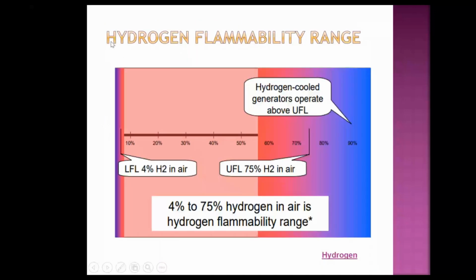Now, coming to the hydrogen flammability range, hydrogen is a very dangerous gas because it has a wide flammability range. If you observe this diagram, 4% to 70% hydrogen mixed in the air will catch fire. Below 4% or above 70%, it is not flammable. Right? That is why in the generator core, they use more than 80% hydrogen. They maintain more than 80% concentration in the hydrogen core.